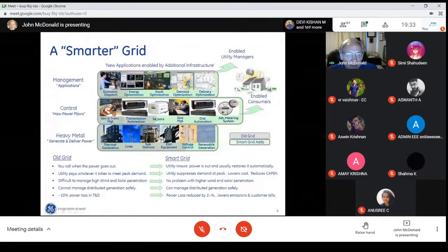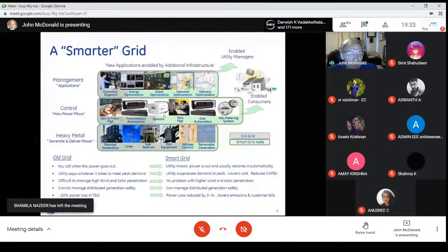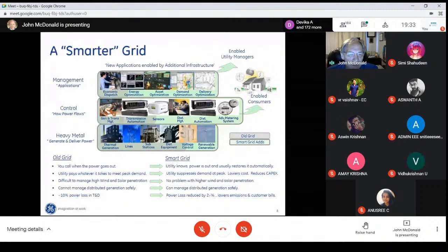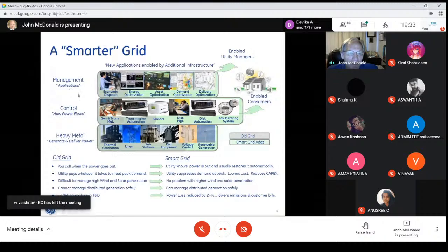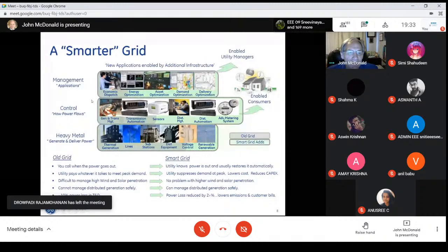Let's go up to the middle here. You see sensors is shaded halfway. Well, we've been adding instrumentation to the grid for many years, but what's different today is we have a lot of specialized sensors that give us very valuable information. As an example, the sensor I'm showing here, I would connect to a transformer, and I would take the oil from the main tank of the transformer and have that oil go through the inside of the sensor. And the sensor can detect dissolved gases in the oil of that main tank. This is called DGA, dissolved gas analysis.